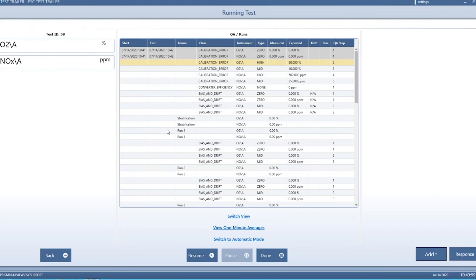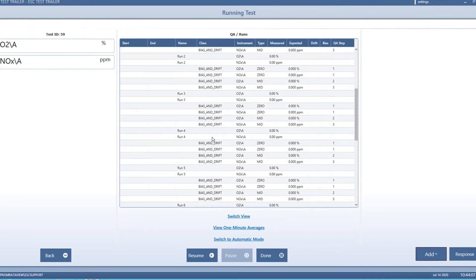Now it's running the O2 at high — it's expecting 20% and we're at zero since this is a demo. If at any point you're happy with the numbers and good to go, you can hit accept values. That'll accept whatever the current value is and end the step, going on to the next one. You can also adjust the time as needed. If you hit accept value and it fails, you can hit reset and run that step again if you had some sort of problem. That's the basic idea of the test running — guided and easy to use yet flexible.